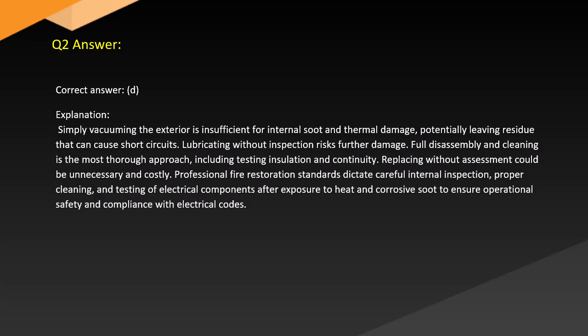Simply vacuuming the exterior is insufficient for internal soot and thermal damage, potentially leaving residue that can cause short circuits. Lubricating without inspection risks further damage. Full disassembly and cleaning is the most thorough approach, including testing insulation and continuity. Replacing without assessment could be unnecessary and costly. Professional fire restoration standards dictate careful internal cleaning and testing of electrical components after exposure to heat and corrosive soot to ensure operational safety and compliance with electrical codes.